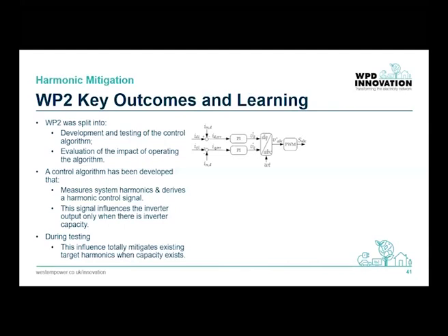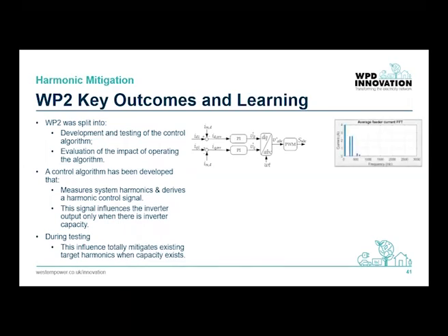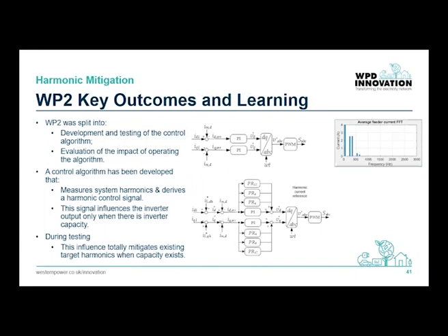And if we were to measure feeder current and analyse harmonics, we'd see a chart looking something like this. The harmonics are due to loads on the network. We can clearly see 5th, 7th, 11th and 13th harmonic components. From this development work, a controller structure and associated algorithms have been developed that act on these particular harmonics. This has been designed such that the intended mitigation increases according to network harmonics and acts based on inverter available capacity.